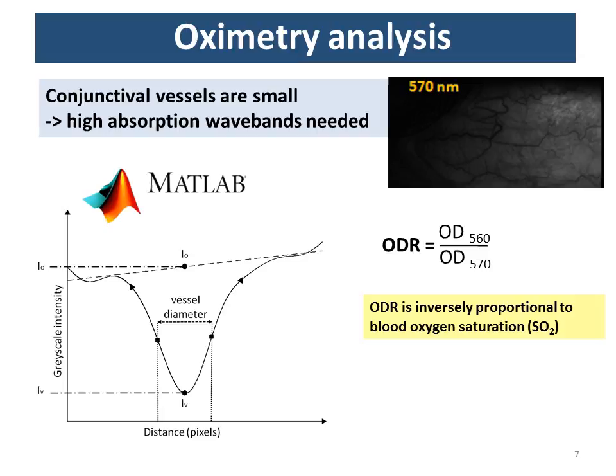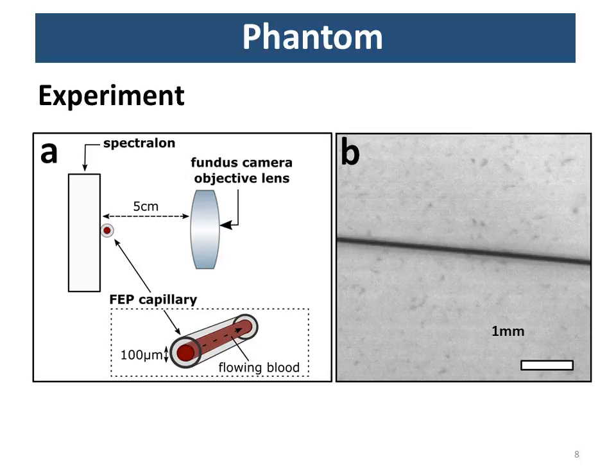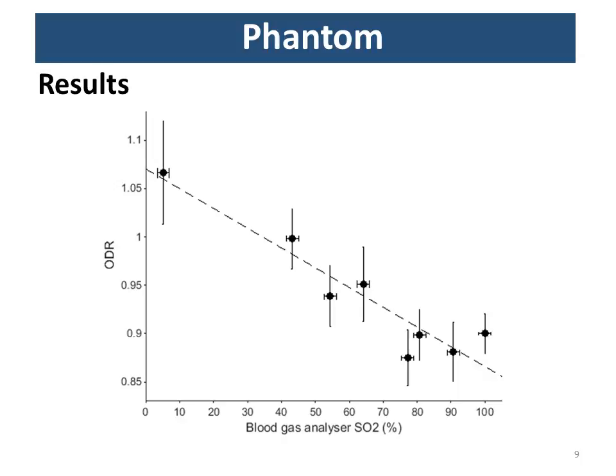To validate the oximetry capability of these wavelengths, we constructed a simple phantom consisting of a piece of Spectralon to simulate the sclera — a white diffuse reflectance material with uniform reflection in the visible wavelength range — and a 100 micrometre FEP capillary filled with ex vivo flowing blood. We found that optical density ratio did indeed follow an inversely proportional relationship to oxygen saturation as measured by a blood gas analyser.